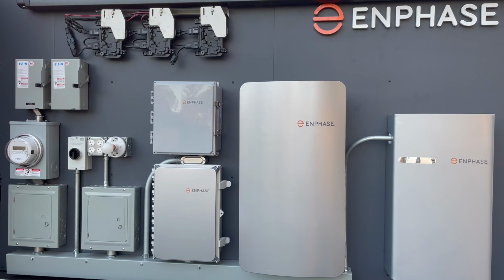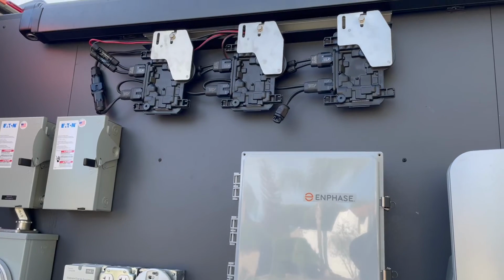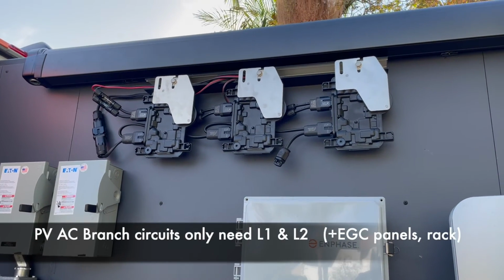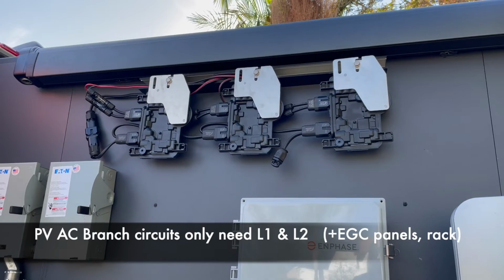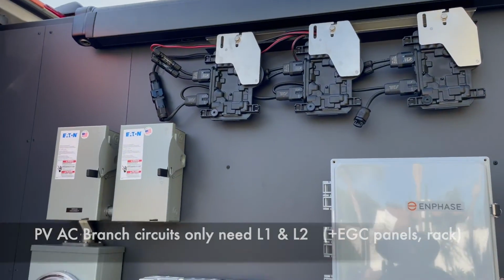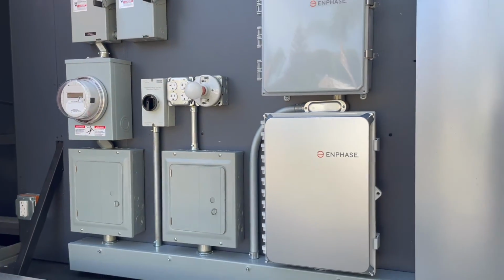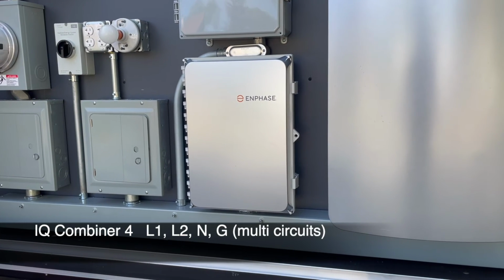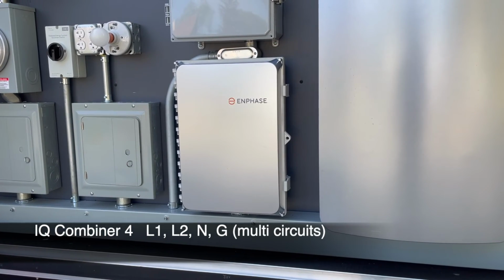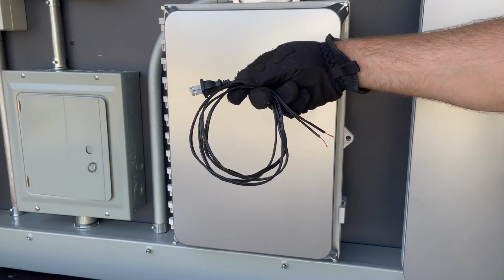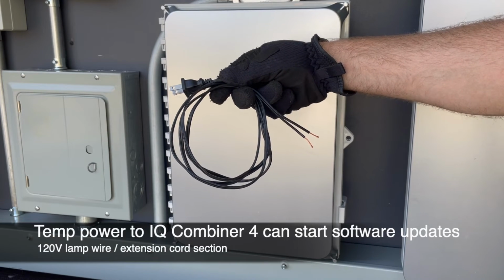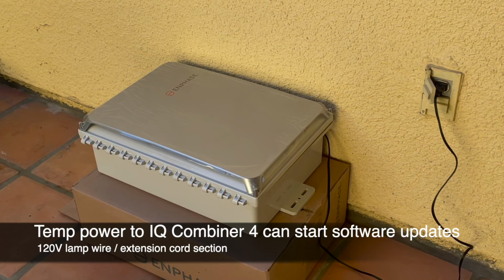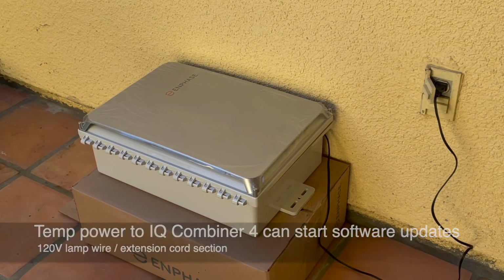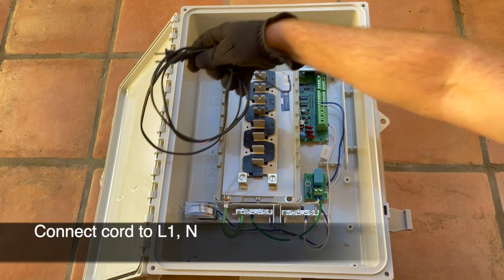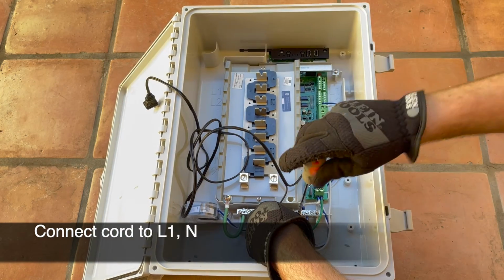A few professional tips. From the roof down, microinverter branch circuits only need L1 and L2, but you'll also run an equipment grounding conductor for the solar array and racking. In the IQ Combiner, neutral and ground wires are also required. To reduce commissioning time, you can start software updates on an IQ Gateway with temporary power while you complete other work at the site. Connect a 120 volt cord to L1 and neutral.